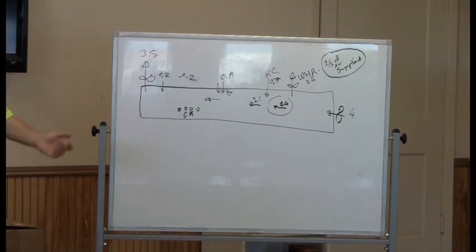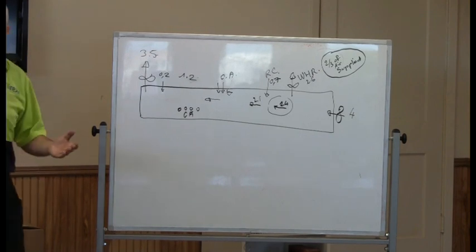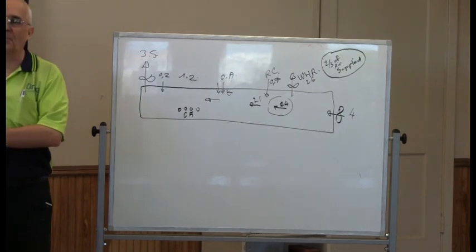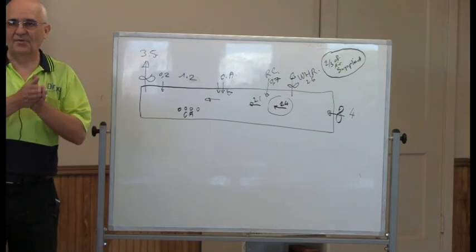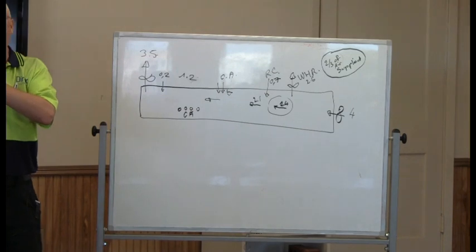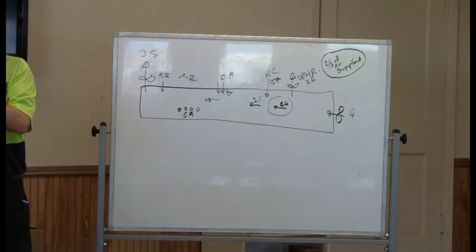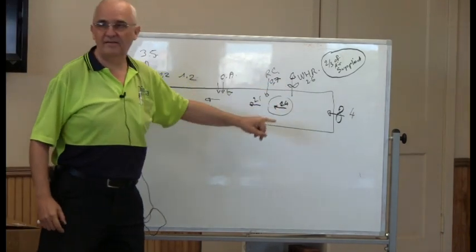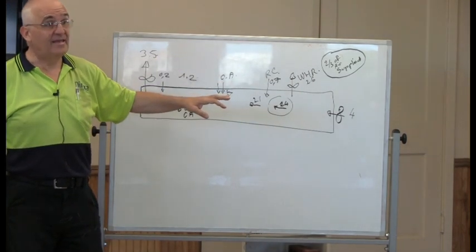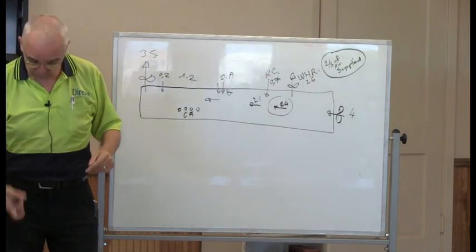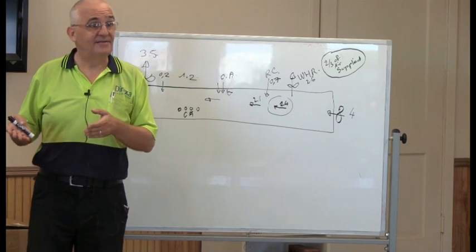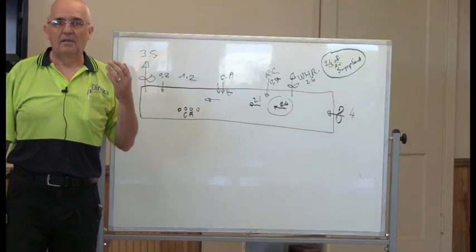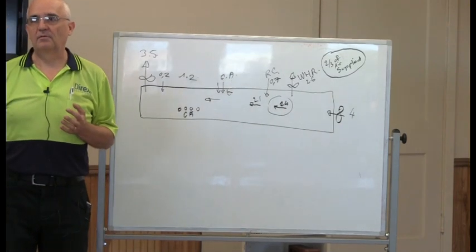And sometimes we can make it. But if you see a degradation in quality or in heat distribution, don't accuse the burner right away. Because if it was doing the right job with the right amount of air, and you lose one of the airflows, you need to find a way to get that airflow right. For example, if at 16 cars per day the dryer needs more heat, and I start to increase that fan for more airflow, don't, because you're going to shoot yourself in the foot. You have to find another way, if possible. You can create your own misery.